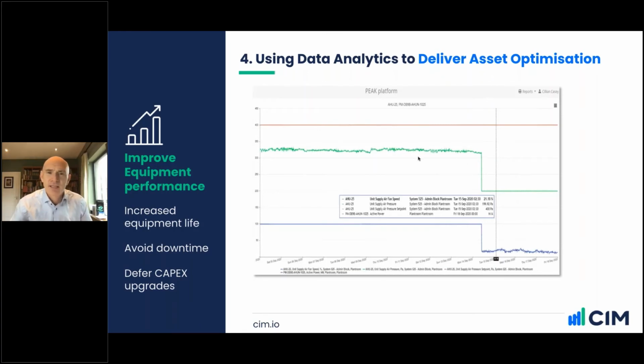In this instance, the Peak platform identified it as an operational inefficiency. But when we asked the technicians to go down, it turned out that the static air pressure sensor had just come out of the binder pocket that it was sitting in. So the technician reseated it, and the pressure came back into control, started modulating at maybe 200 pascals. And you can see then immediately the VSD on the supply air fan dropped way back. It went from 100% back to something like 20%.